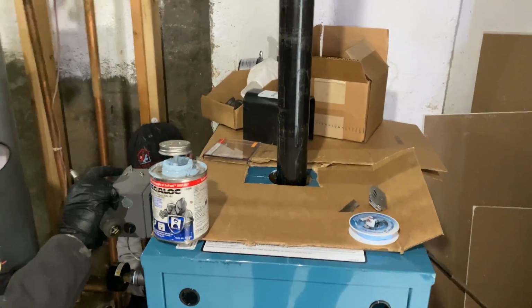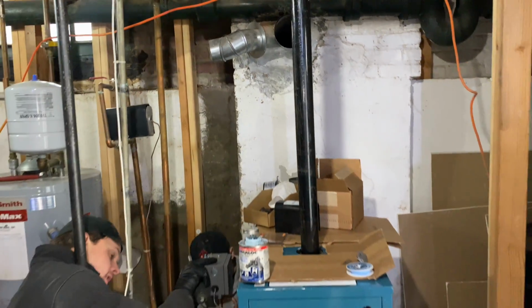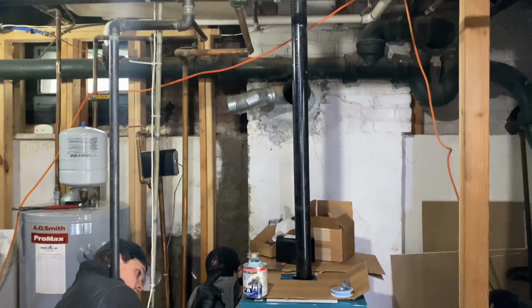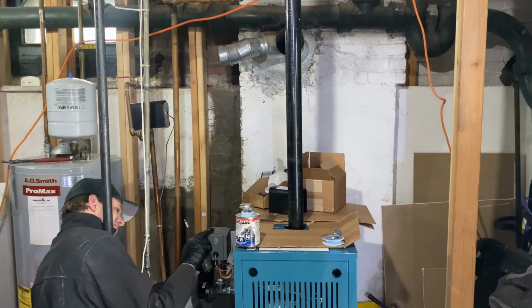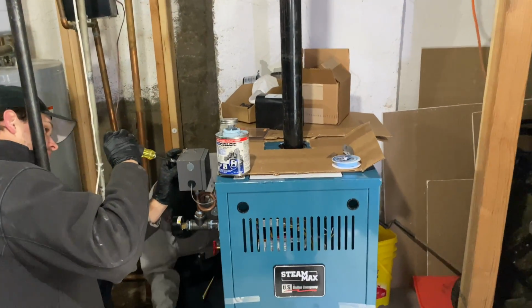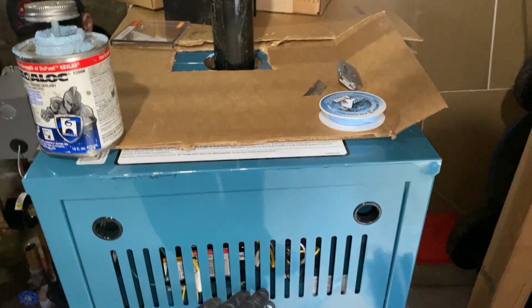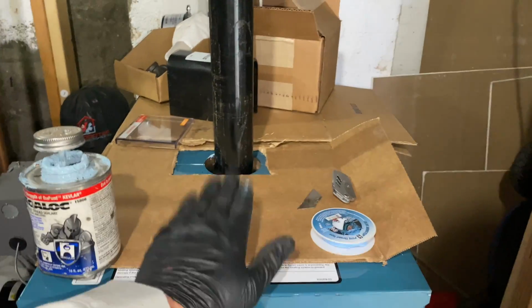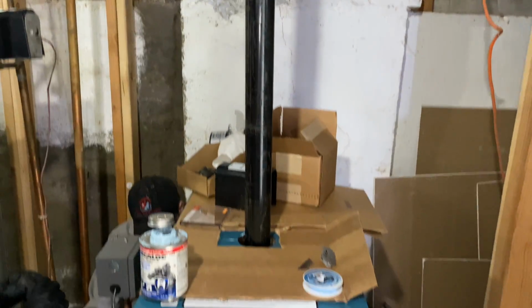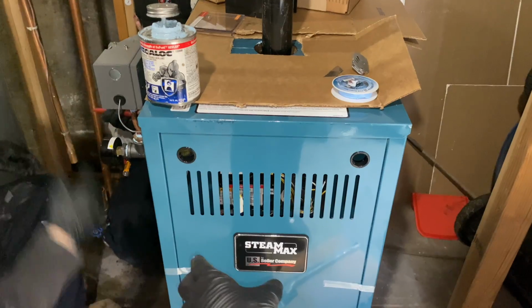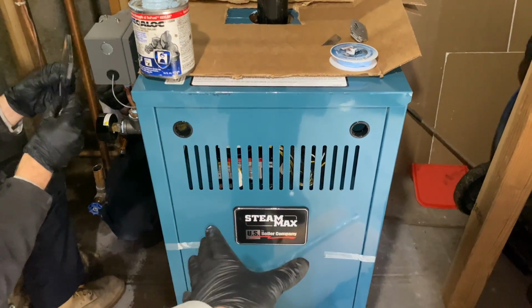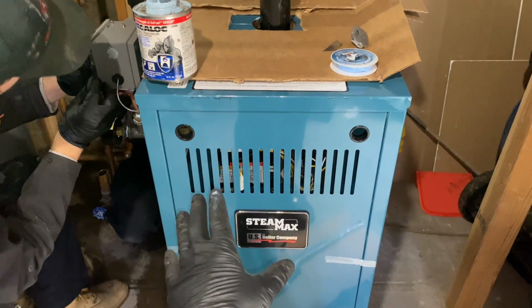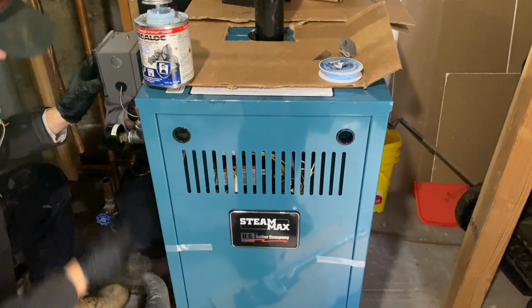All right, ladies and gentlemen, I put in my first piece, and I'm really thinking about using this piece to create the world's driest steam. If you open up the installation manual, you need to be a minimum of 18 inches from the top of the boiler. This is not the top of the boiler. Top of the boiler here, 18 inches. The reason is that water is violently boiling in that pot that you don't see when it's on and heating, and that's getting all the way up here, by the way.